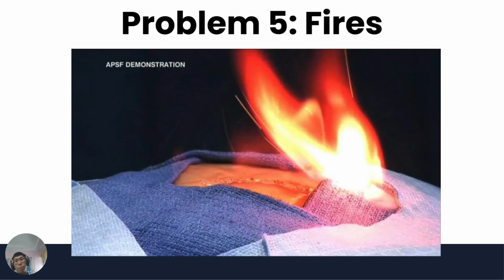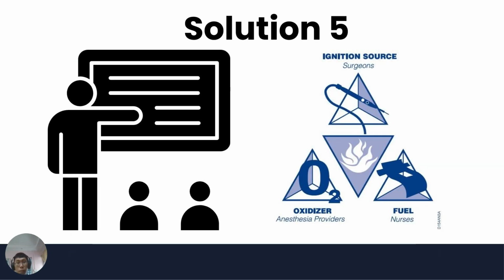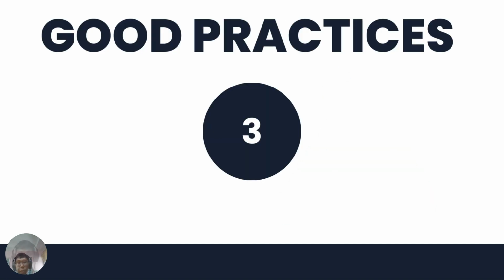The fifth problem is fires. Flash fires have occurred due to the ignition of flammable materials in an oxygen-enriched environment in the operating room after coming into contact with the ESU, resulting in fatal injuries to patients. The solutions to fires: surgical staff awareness, fire drill training, and identifying high-risk procedures can decrease the chances of fire. The ESU should not be used in places with flammable liquids and materials or places high in oxygen.